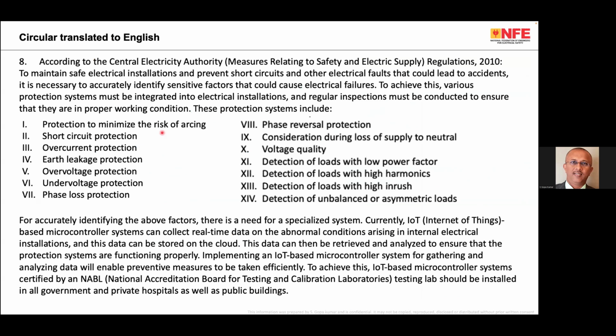The government notice says, according to the Central Electricity Measures Relating to Supply Regulation 2010, to maintain safe electrical installation and prevent short circuits and other electrical faults that could lead to accidents, it is necessary to accurately identify sensitive factors that could cause electrical failure. To achieve this, various protective systems must be integrated into electrical installation and regular inspections. These protective measures should be, you can see here, protection from minimum arcing, and then the final is asymmetric load. Now, if you further read, implementing an IoT based microcontroller system for gathering and analyzing data will enable preventive measures to be taken efficiently.